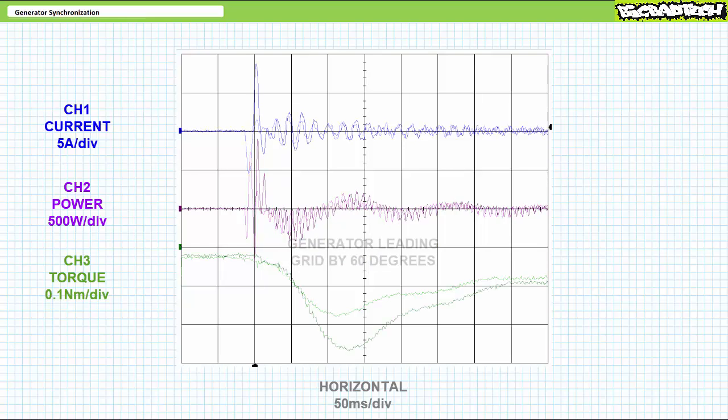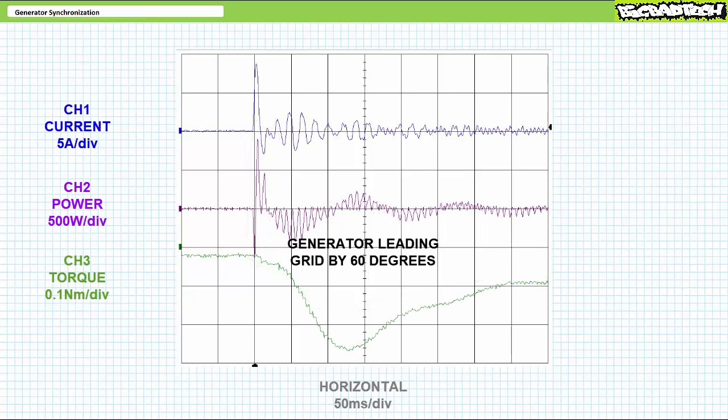Let's make it worse. Consider what happens when I close the contactor when the generator matches the grid phase shift, frequency, and voltage magnitude, however the rotor is an increased 60 degrees ahead of the stator at the time of closure. As previously, electrically, there's a momentary surge of current and electrical power out of the machine, only more dramatic in magnitude and sustained in nature. Again, mechanically, the shaft experiences a surge of counterclockwise braking torque, only greater in strength. Given the rotor is further ahead this time, the grid brakes the rotor more aggressively. A greater mismatch results in greater undesirable electrical and mechanical transients.